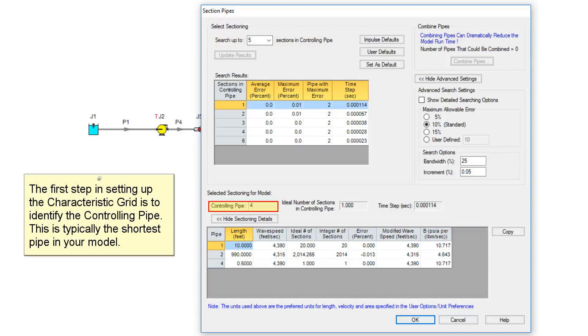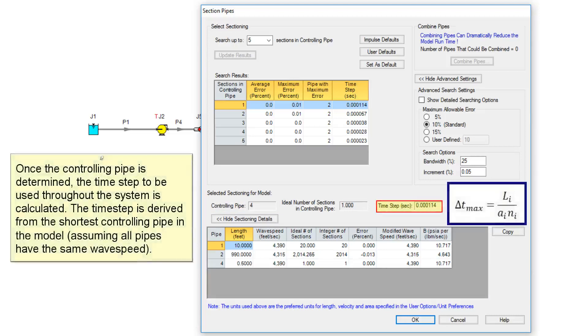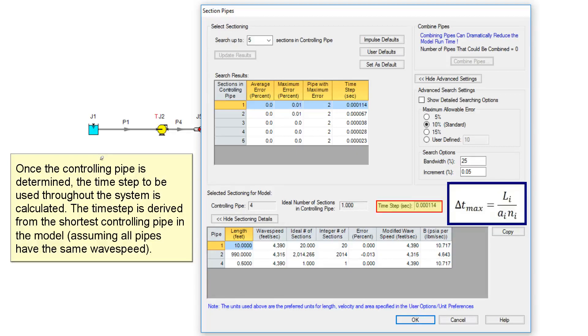The first step in setting up the characteristic grid is to identify the controlling pipe. This is typically the shortest pipe in your model. Once the controlling pipe is determined, the time step to be used throughout the system is calculated. The time step is derived from the shortest controlling pipe in the model, assuming all pipes have the same wave speed.